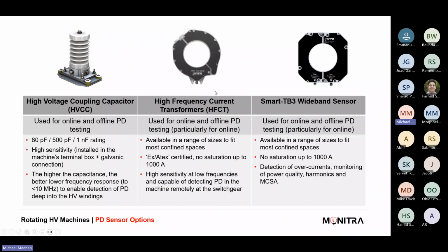High frequency CTs. We can also use these to detect PD, and they'll be connected to the cables at the cable screen region. And we've also got a patented way of measuring PD on VSD fed machines. Typically, a VSD fed machine wouldn't have a high voltage coupling capacitor, because of the transient pulses that are generated. So a way of measuring PD on a VSD machine in a safer way is to use a high frequency CT, so you're not directly coupled to the HV circuit and putting yourself in those transient voltage conditions.